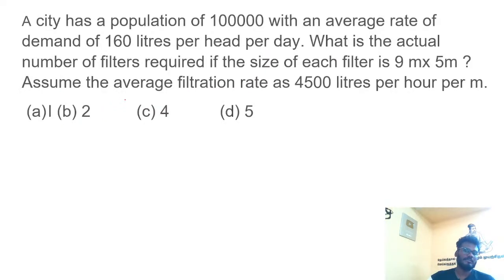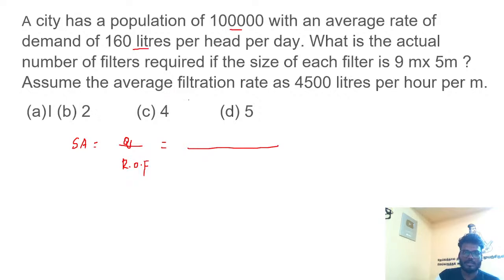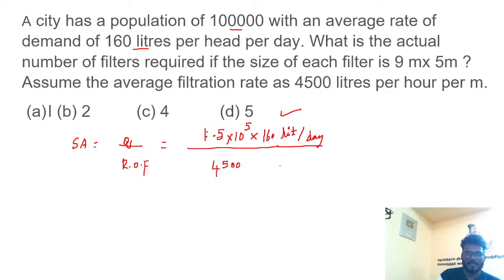We are asked to find the area or number of filters. We can use the expression: surface area = discharge Q / rate of filtration. The discharge Q is designed based on maximum daily demand. Maximum daily demand = population × per capita demand. Population is 10⁵ and per capita demand is 160 liters per day. Using a factor of 1.5, the maximum daily demand = 1.5 × 10⁵ × 160 liters per day, divided by 4500 liters per hour per meter square.